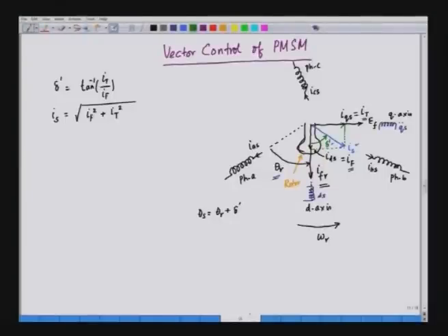We can show that in this phasor diagram. So, here we can see that IDS is helping the rotor flux, that is IFR. IDS and IFR are in the same direction. Now, if we take a situation where we have the field current here, IFR, and we need to go for flux weakening. For flux weakening, the resultant flux has to be reduced.